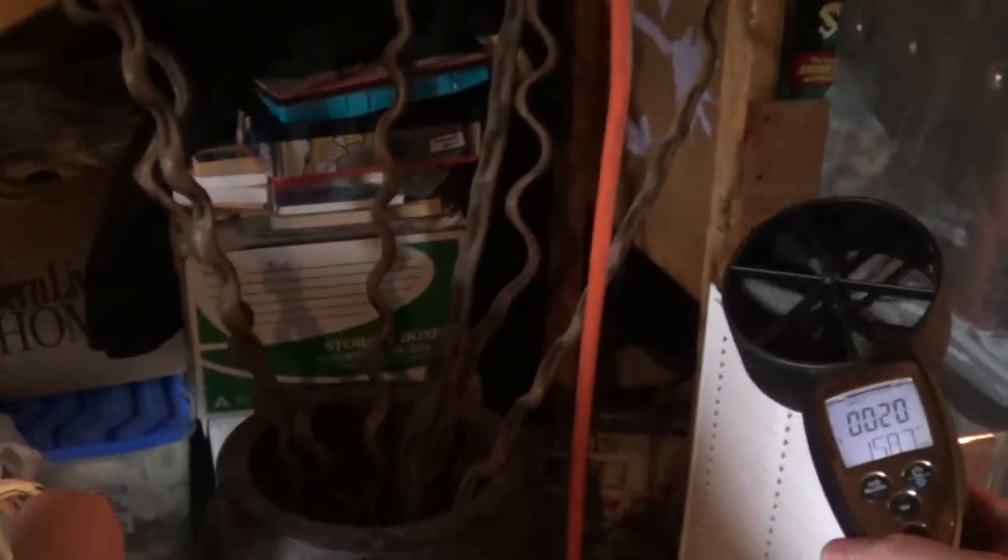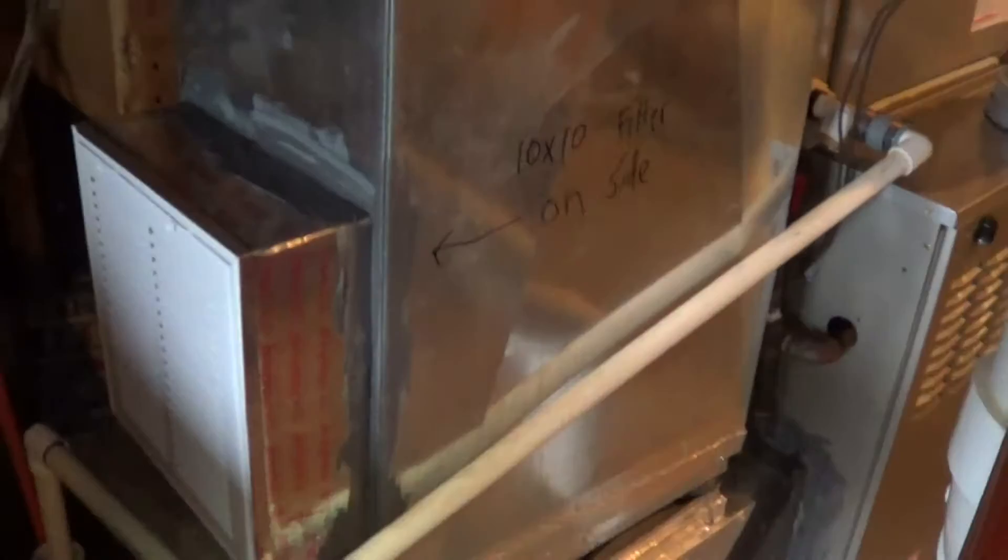So I add the two, I'm about 1450 CFM. So the accurate measurement is actually a little bit better than the fast and dirty which was just checking static pressures.